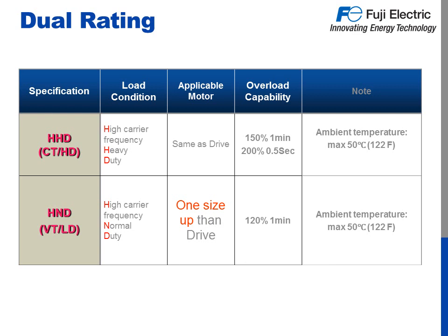The Frenic Ace is a dual rated drive, meaning you get two different capacity options in one drive. HHD, also known as High Carrier Frequency Heavy Duty, Constant Torque and General Purpose, offers an overload of 150% for 60 seconds and 200% for a half second. HND, also referred to as High Carrier Frequency Normal Duty, Variable Torque and Fan and Pump Duty, offers 120% overload for 60 seconds, making it ideal for most pump applications. Both HHD and HND are designed for ambient temperatures up to 122 degrees Fahrenheit.